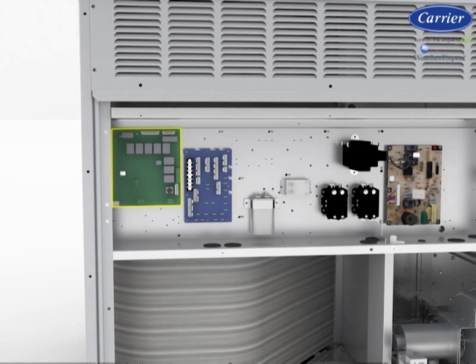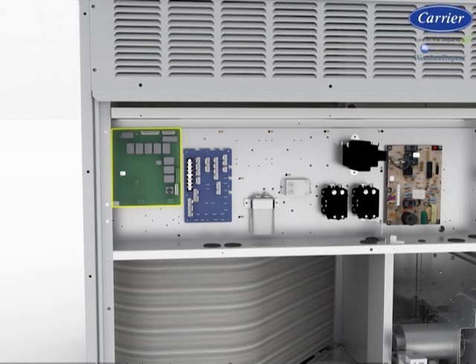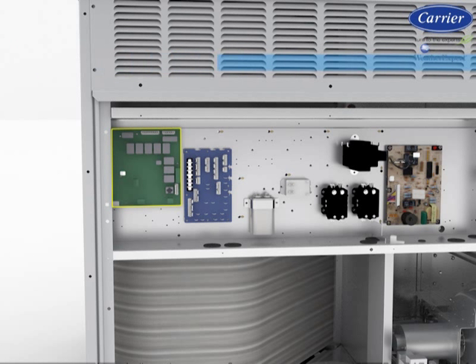Carrier's RTU Open Controller integrates the rooftop unit to an existing or newly designed building automation system without needing complicated translators or adapter modules. The RTU Open Controller speaks four of the most common building automation system languages: BACnet, Modbus, N2, and LonWorks. When factory provided, the BACnet protocol is standard, and with a simple dip switch adjustment, access to the other network protocols is available.